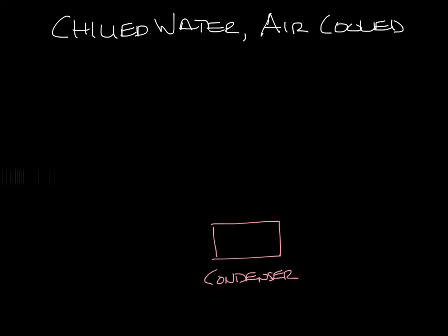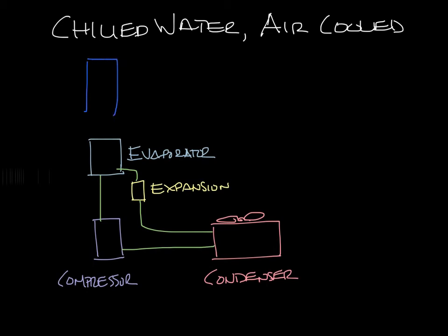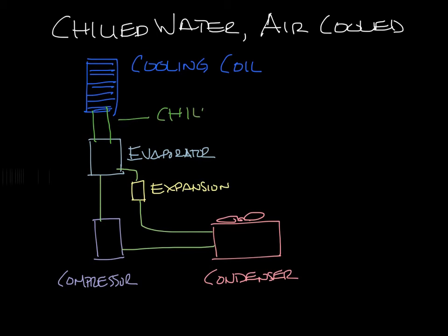Let's draw in our air-cooled condenser and our compressor, our evaporator, and our expansion device. Now let's draw the refrigerant route from the compressor to the condenser to the expansion device to the evaporator and back to the compressor. You also have a chilled-water coil. The evaporator cools down water that is circulated to the cooling coil, which cools down the supply air. The supply air transfers its heat to the cooling coil, which warms up the water, and the water travels back to the evaporator to be cooled down again.